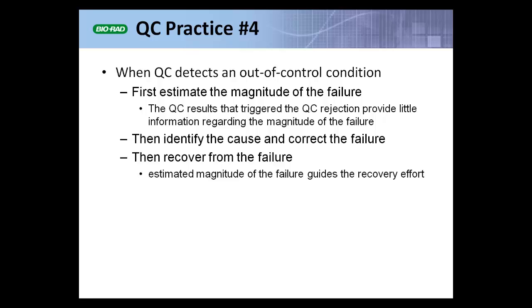This practice is more about trying to minimize the cost of rework — unnecessary rework in the laboratory, cost of poor quality. It's more focused on the laboratory. The QC results that triggered the QC rule rejection provide very little information regarding the magnitude of the out-of-control condition, so it's a good investment to do a better job of assessing its magnitude when it's detected.